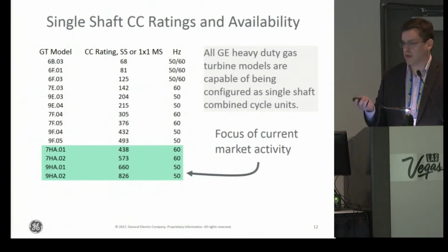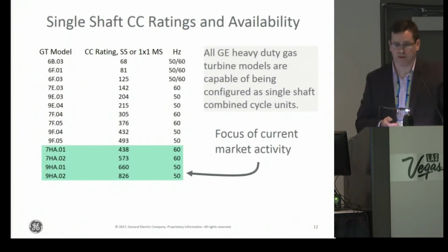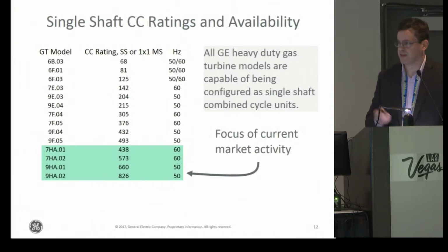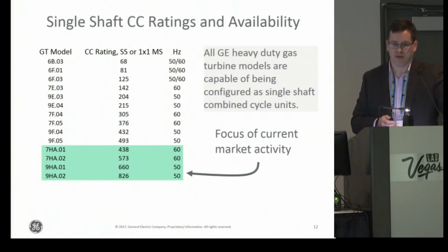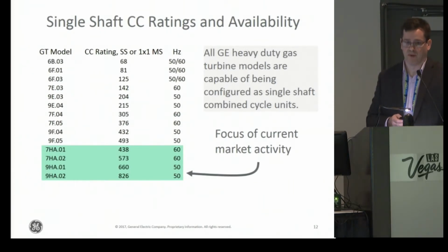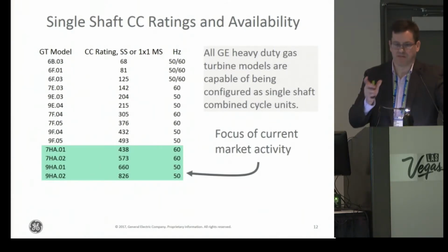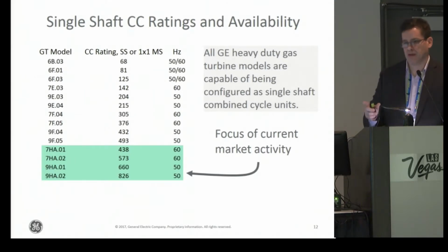You can see how big they are in the 50 hertz world now, pushing over 800 megawatts for a single shaft combined cycle. And on the 60 hertz, we're getting closer to the 600 megawatt range for one gas turbine, one steam turbine, and one generator. So that combination of flexibility and also, in a lot of ways, the reliability too, to be able to produce base load power, that is a very big advantage of the single shaft, in my opinion.